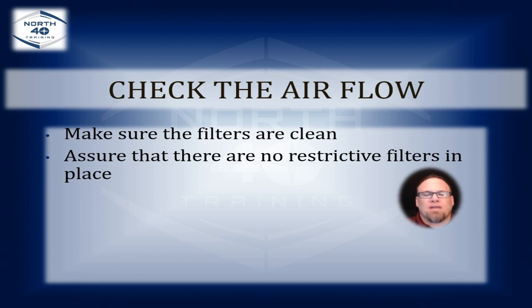Now, there are some filters that came out in the late 80s, maybe mid 90s. We used to call them Paul Harvey specials. They were washable filters, extremely tightly woven, crosshatched with plastic mesh with some foam in between them. They were so restrictive that you could literally take and put a water hose up next to it and nothing would come out the other side, maybe a little drizzle. So you know airflow is not moving through there. Restrictive filters are probably one of the easiest things to correct on the job site that will make the biggest impact on the customer's comfort level.